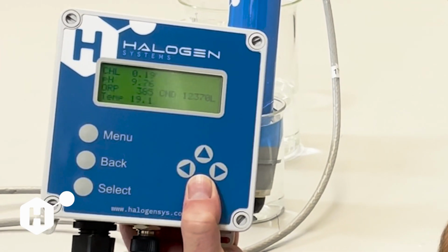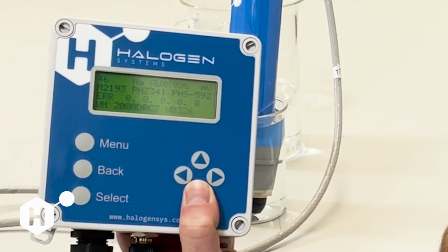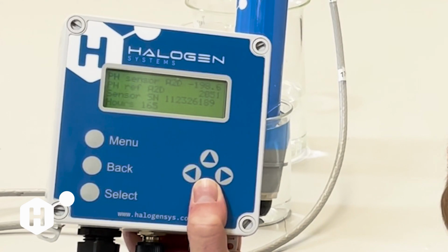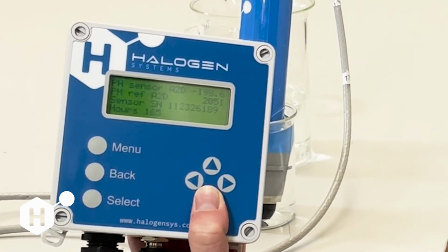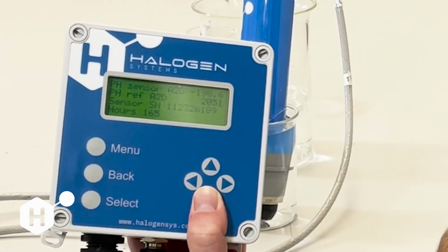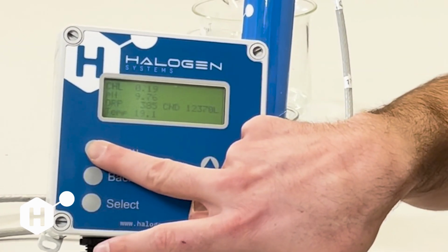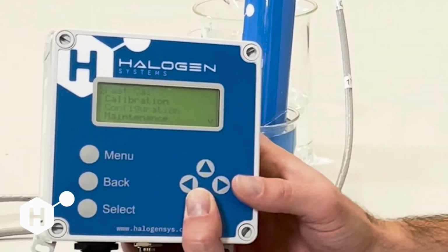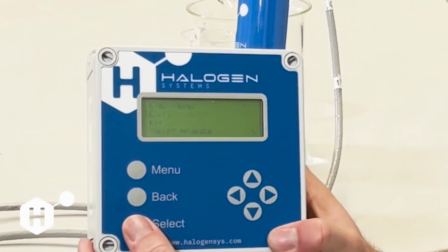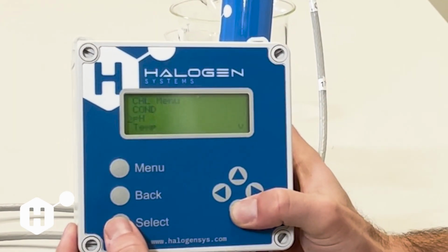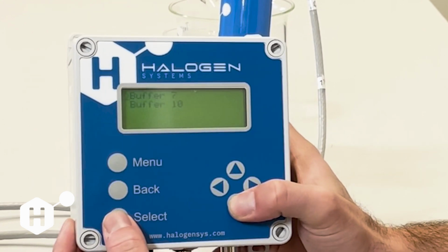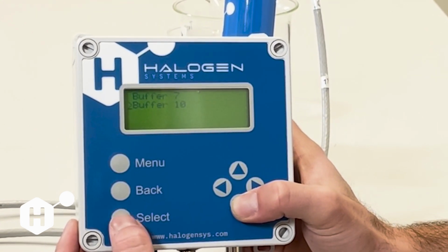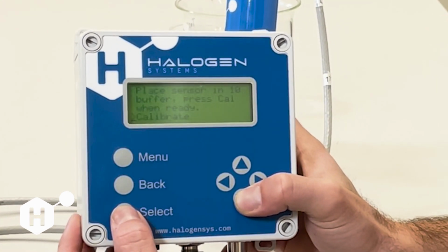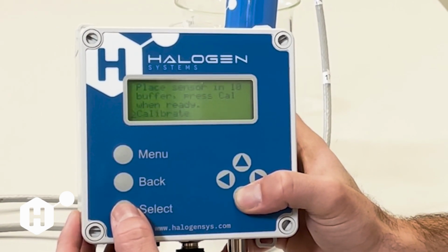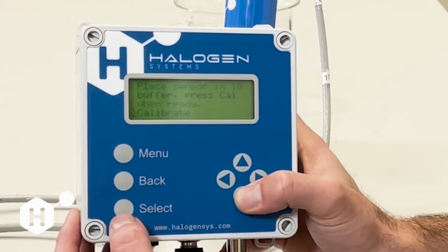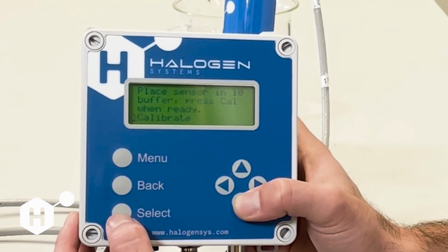So we're at 9.76. We're getting pretty close. So I'm going to go ahead and take a look here. We're still at negative 198.6. So to me, this sensor stabilized pretty quickly. So I'm going to hit menu. We're going to go down to calibration. We're going to go to pH, 2-point buffer cal, and we're going to go to buffer 10 and hit select. It's going to tell us to place the sensor in the 10 buffer. However, we're already in there, so we're feeling pretty comfortable with it, and I'm going to go ahead and hit calibrate.